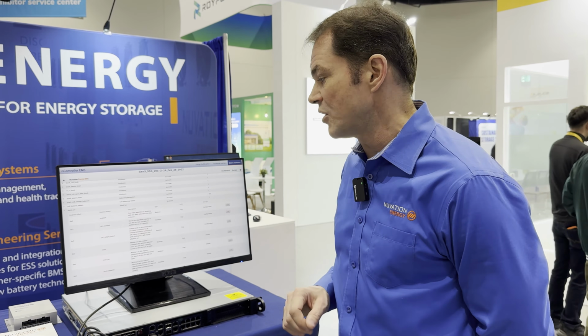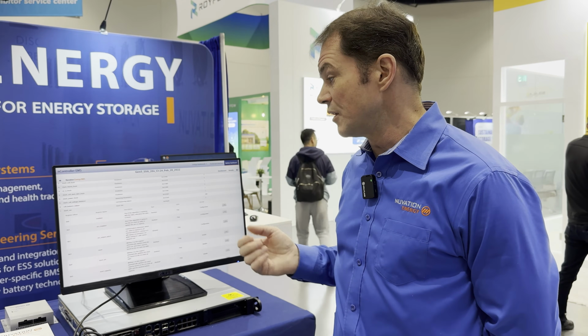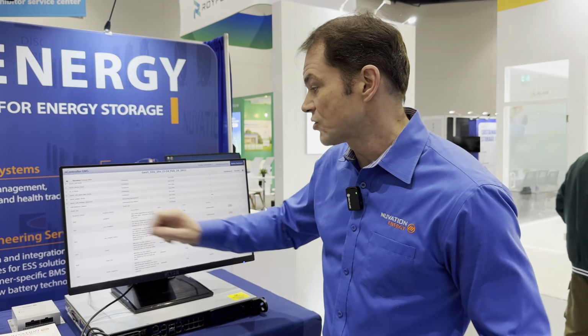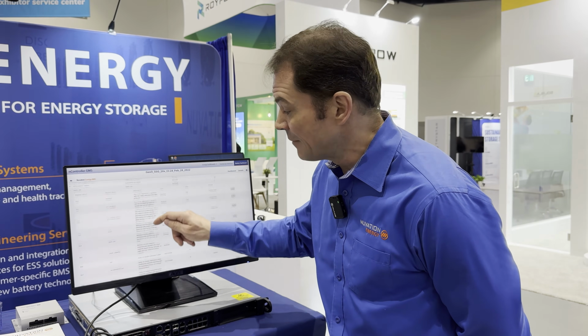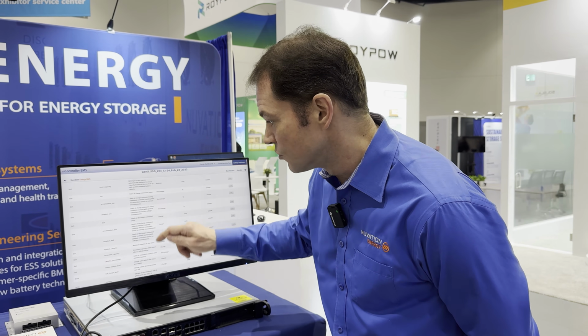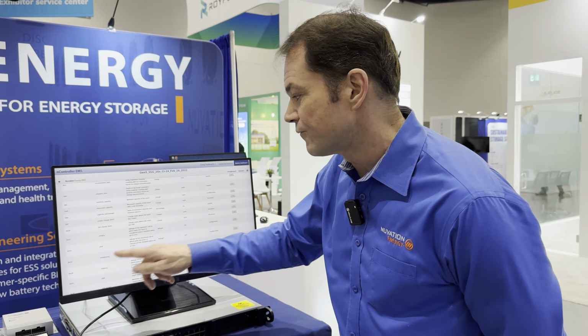This is for an application where you're not hitting V full or V empty inside of the system — say you're doing frequency regulation or PV smoothing, something like that. Then you'd want to enable that open circuit voltage and have adaptive state of charge information on top of your coulomb counting. As another example, let's say we wanted to real-time change our V empty or V full registers.